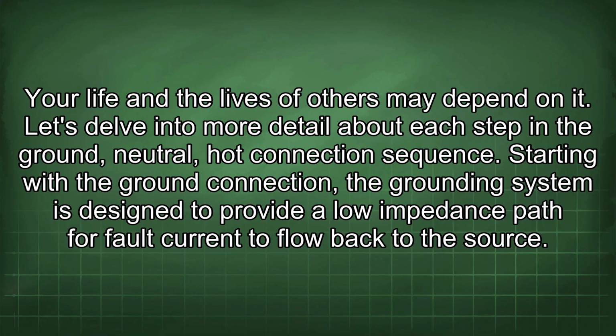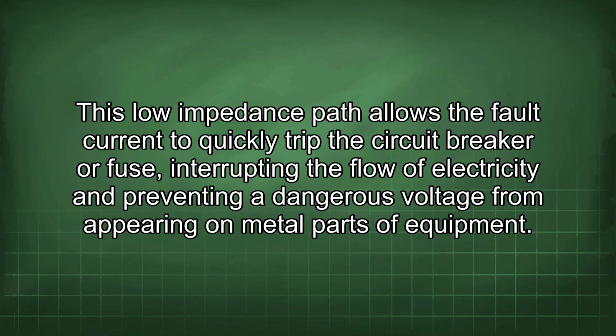Starting with the ground connection, the grounding system is designed to provide a low impedance path for fault current to flow back to the source. This low impedance path allows the fault current to quickly trip the circuit breaker or fuse, interrupting the flow of electricity and preventing a dangerous voltage from appearing on metal parts of equipment.